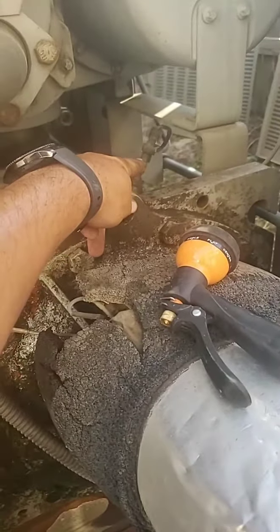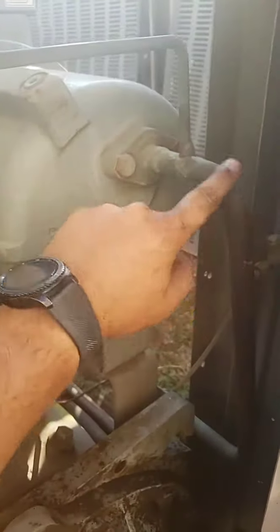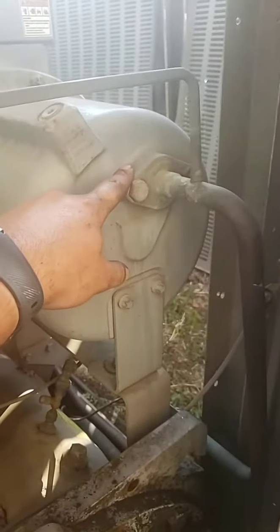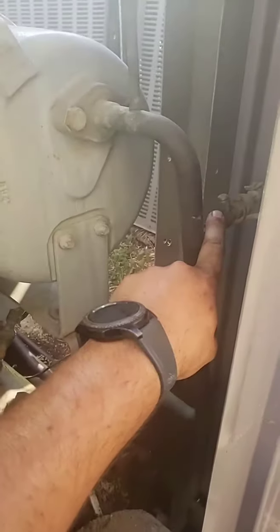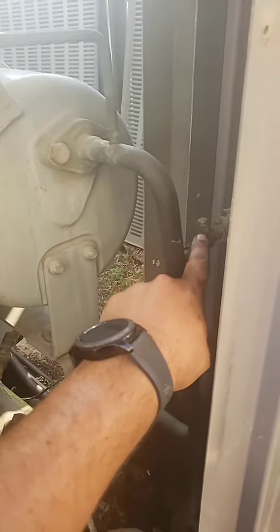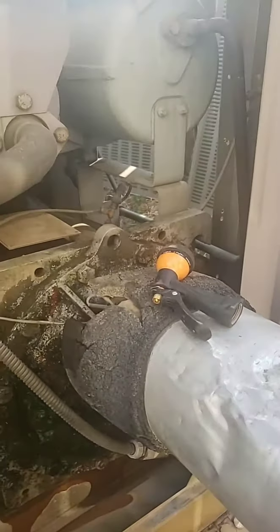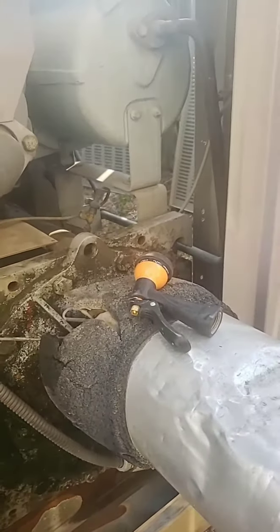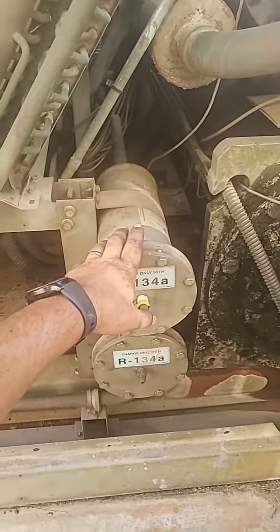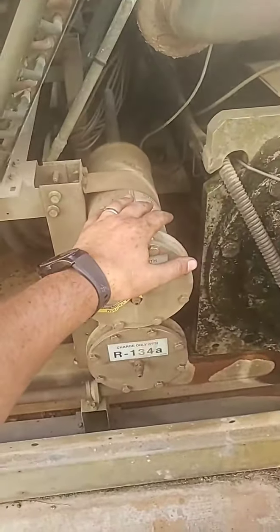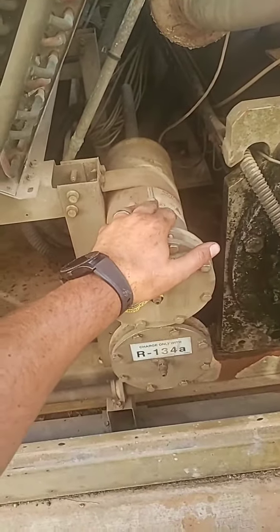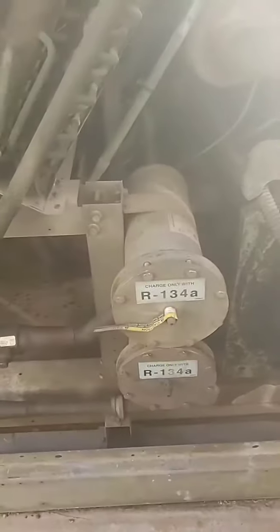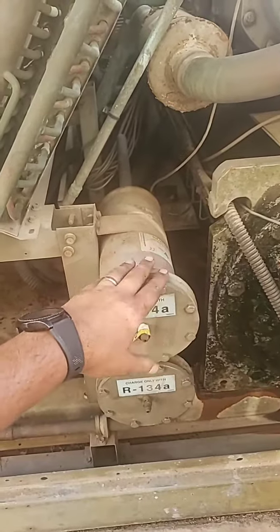Right there is your evaporator transducer. Right here, this is the motor cooling. This is the backside of the motor cooling circuit where it comes in to cool down the motor. This is your economizer transducer. So this is where it's monitoring where the economizer pressure is, and that plays a big role when they start looking at oil pressure differentials. That's why that's there. These are your liquid line dryers. They've got dryer cores inside. I just did an IGTV video this week on how to change these, so feel free to look at that and see what it's like to open one of these up and change it.